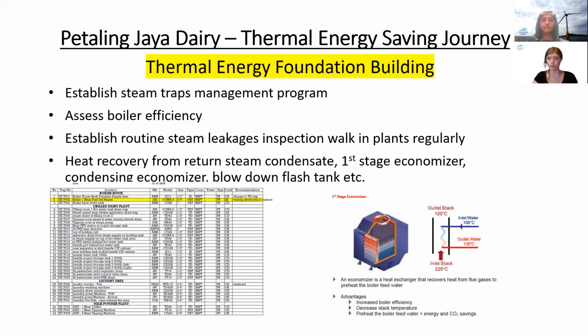For thermal energy foundation building, what we have done is establish a steam traps management program. From the table below, you can see we conduct steam traps assessment yearly. If we find any steam traps which are not working, we will replace them and restore them back to basic condition. When we assess our boiler efficiency, we also establish routine steam leakage inspection walks in the plant regularly.